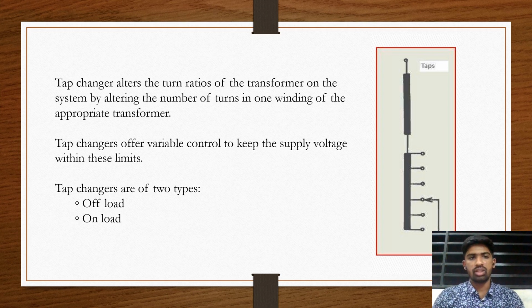These tap changers are of two types. One is the off-load tap changer, sorry, the off-circuit tap changer, and the other one is called the on-load tap changer. The off-circuit tap changer is utilized in situations in which a transformer's turn ratio does not require frequent changing, and it is permissible to de-energize the transformer system. Whereas the purpose of the on-load tap changer is to regulate the output voltage of a transformer. It does this by altering the number of turns in one winding and thereby changing the turn ratio of the transformer.